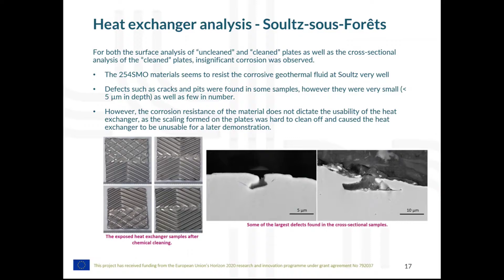So we are going to focus now on the scaling phenomenon in the heat exchangers at Soultz-sous-Forêts. Soultz is located in the upper Rhinegraben in eastern France, and the granite is harnessed at a depth between 4 and 5 kilometers. There we find brine with a high salinity, around 100 grams per liter, containing mostly sodium and chlorine, and with a temperature around 160 degrees centigrade. Next, please, Dagur.